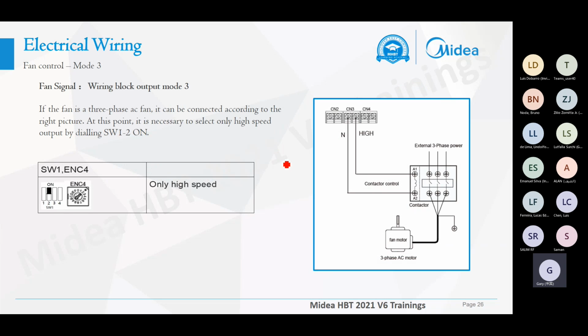And for the three-phase motors, we can only set the high speed. And the dial switch, 1-2, should be selected on. That's on. So if your AHU selects the three-phase motors, there is only one speed available, just the high speed.